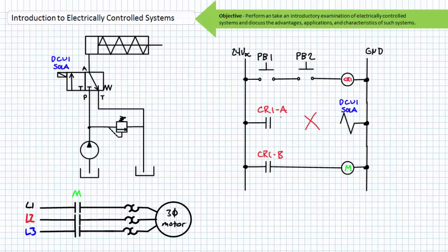If both push button 1 and push button 2 are simultaneously closed, control relay CR1 would energize and the associated contacts would change state. However, the broken wire in the second rung of the ladder logic diagram would not allow DCV1 solenoid A to energize, yet the third rung would allow the drill motor to rotate. In this case, the drill would rotate, but the cylinder would not extend. Consider loss of the L2 phase in the three-phase power supply. If push button 1 and push button 2 were simultaneously closed, the cylinder would extend, yet with a loss of one of the phases inside of a three-phase AC power system, the three-phase AC motor would have difficulty starting.